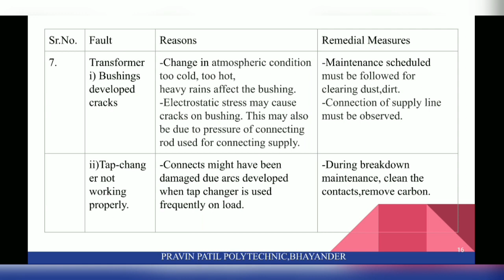And next fault for transformer is tap changer not working properly. Reasons are contacts might have been damaged due to arc developed when tap changer is used frequently on load. And remedial measures are: during breakdown maintenance, clean the contacts, remove carbon.